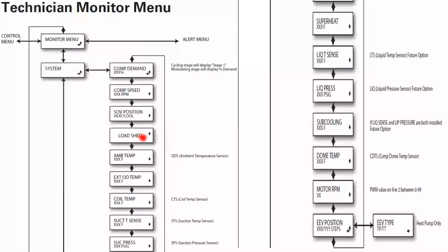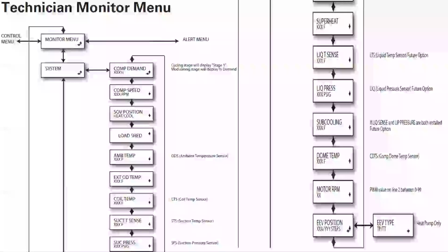We can see if we have load shed connected. Here's our ambient temperature. This is for future use. We don't have that connected yet. I'm sorry. We're going to be looking at our coil temp in the outdoor unit. This is just looking at the outdoor unit. Again, TAM9s, I did not put the slide deck in for TAM9s, but the TAM9 menu is pretty similar to this menu. So keep that in mind. You can look at all the TAM9 sensors also.